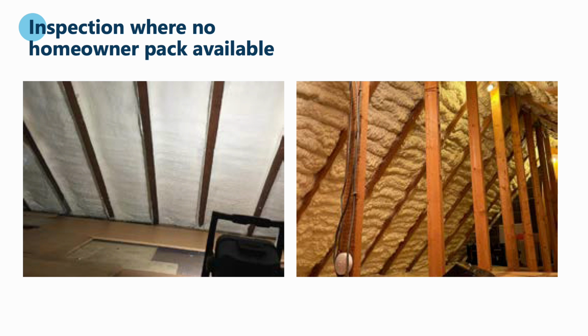The image you see on the left shows a good installation of a closed cell foam, which has a fairly smooth surface, whereas the image on the right is of an open cell foam. Note that the surface finish here is not smooth, but that the thickness is consistent throughout the application. In particular, open cell spray foam has a popcorn-type appearance, which is perfectly normal and acceptable.